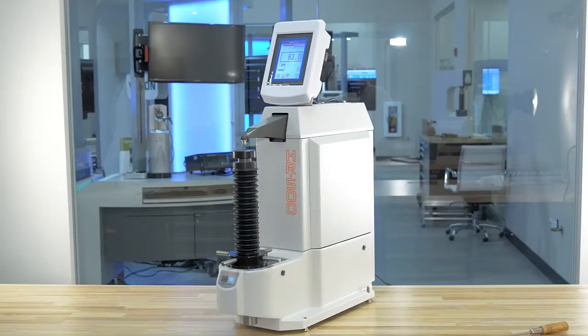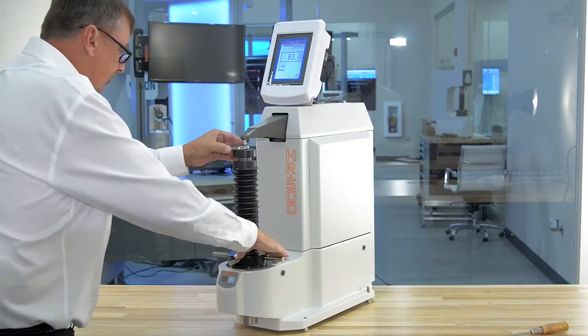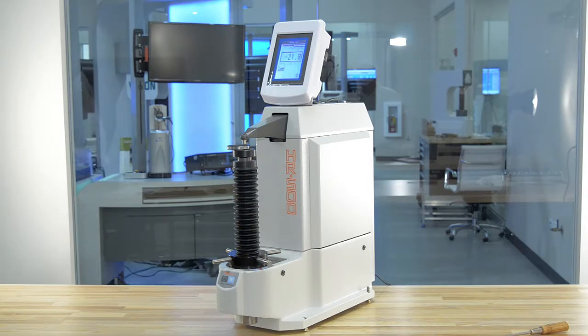The advanced HR-500 series is for the user that wants the most accurate and repeatable results. The projected nose design allows for ID testing down to 22mm with an optional cut down indenter or 40mm for the standard model. The design also lets the elevating screw hang over the edge of the table so that full 8.1 inch capacity is available without cutting holes on this model as well.